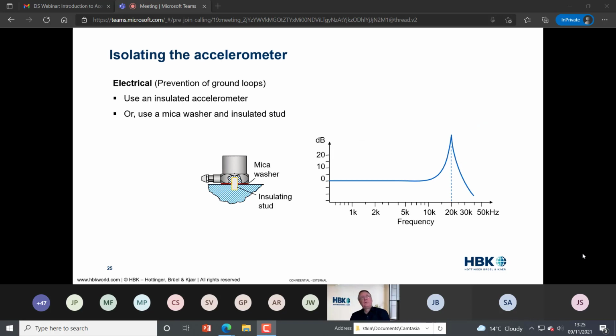Also, if the surface that you're measuring the vibration on is electrically conducting, you might have some difficulties with ground loops or hum, where you've got two earths in the system, one from the case of the accelerometer and one from the real earth. In that case, you need to isolate the accelerometer electrically from the surface it's mounted onto. And there's two ways to do that. Either you can use an electrically insulated accelerometer, or, as is shown on the picture here, you can use an insulating stud and a thin mica washer, which just puts electrical isolation between the ground and the accelerometer.